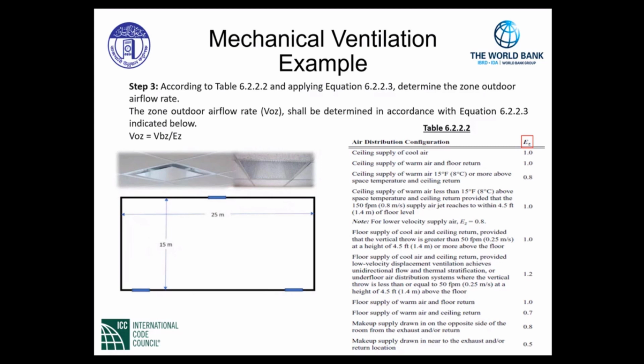We noted that the supply air and the return air are at the ceiling level. This is important to apply this particular table, ladies and gentlemen. By applying this table in conjunction with the equation V sub OZ equals V sub BZ that we've already calculated, we simply divide by what we call the E sub Z factor that's given to us from the table 6.2.2.2.